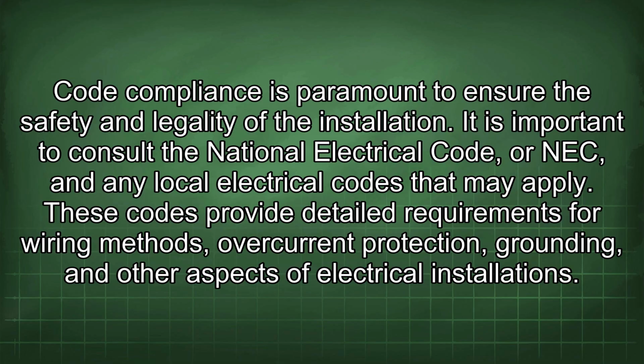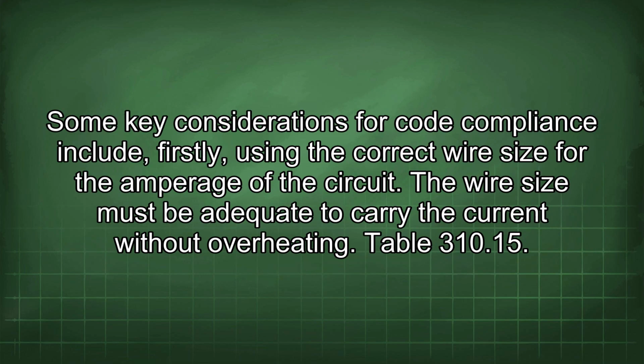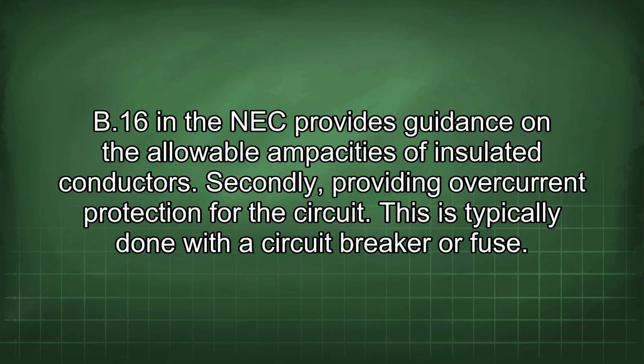Code compliance is paramount to ensure the safety and legality of the installation. It is important to consult the National Electrical Code, or NEC, and any local electrical codes that may apply. These codes provide detailed requirements for wiring methods, overcurrent protection, grounding, and other aspects of electrical installations. Some key considerations for code compliance include, firstly, using the correct wire size for the amperage of the circuit. The wire size must be adequate to carry the current without overheating. Table 310.15(B)(16) in the NEC provides guidance on the allowable ampacities of insulated conductors.